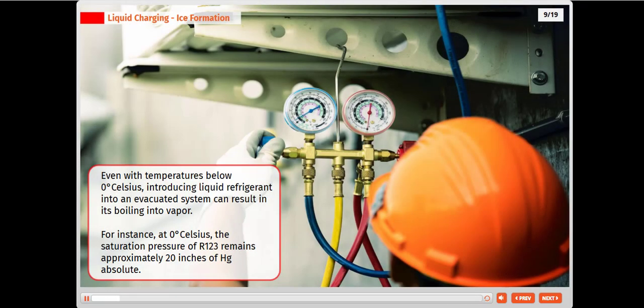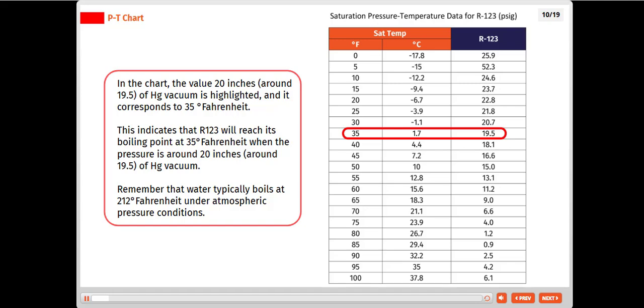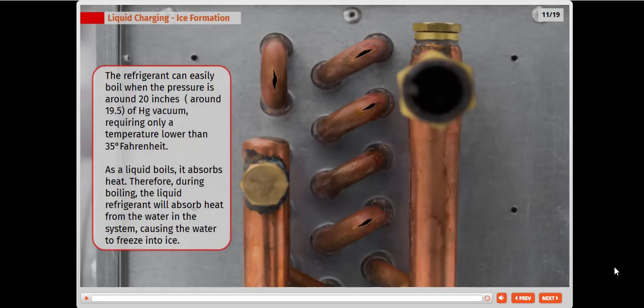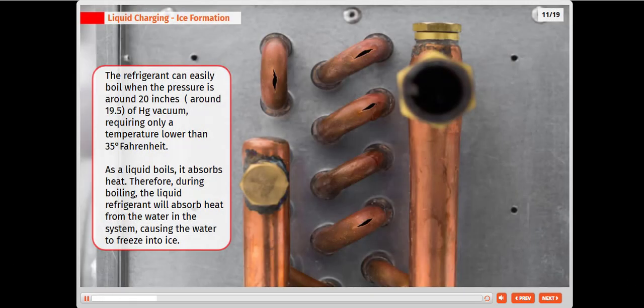Even with temperatures below 0 degrees Celsius, introducing liquid refrigerant into an evacuated system can result in its boiling into vapor. For instance, at 0 degrees Celsius, the saturation pressure of R123 remains approximately 20 inches of mercury absolute. In the chart, the value 20 inches, around 19.5, of mercury vacuum is highlighted, and it corresponds to 35 degrees Fahrenheit. This indicates that R123 will reach its boiling point at 35 degrees Fahrenheit when the pressure is around 20 inches, around 19.5, of mercury vacuum. Remember that water typically boils at 212 degrees Fahrenheit under atmospheric pressure conditions. The refrigerant can easily boil when the pressure is around 20 inches, around 19.5, of mercury vacuum, requiring only a temperature lower than 35 degrees Fahrenheit.